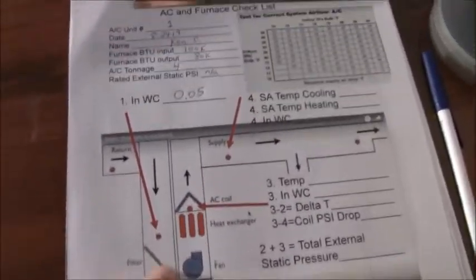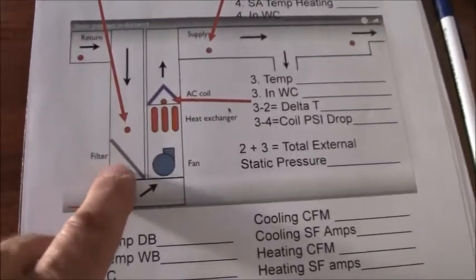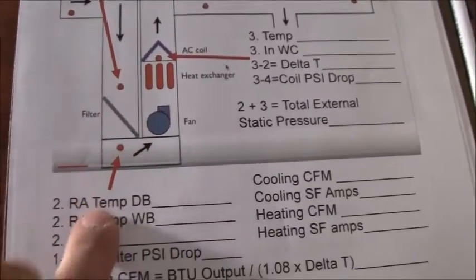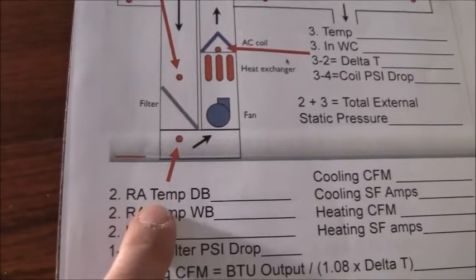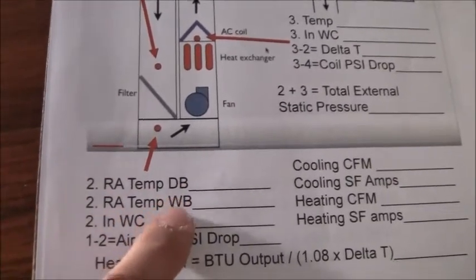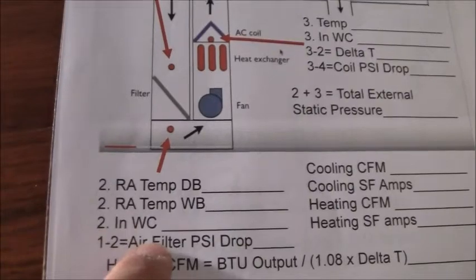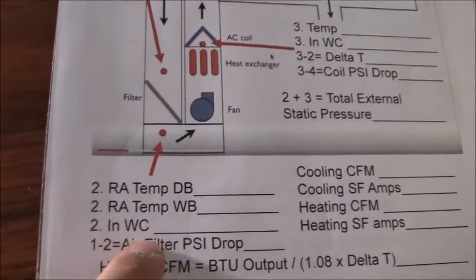0.05. The next one that we want: then you have a filter, then there's the next point right there. We need to know what that is, and we'd like to get the return air temperature, dry bulb, wet bulb, and the inches of water column. So let's start with the inches of water column. On the side of the furnace, over here, I drilled a hole earlier so I could put my reading into. Okay, there it is right there. I found it. I'm going to go in.